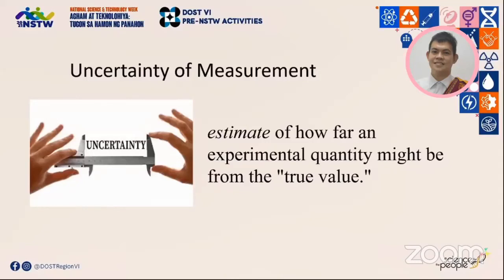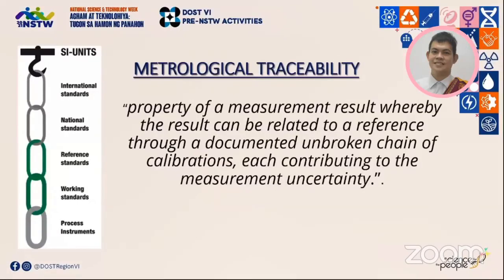Metrological traceability is a property of a measurement result whereby the result can be related to a reference through a documented and unbroken chain of calibrations, each contributing to the measurement uncertainty. Traceability is established through reference numbers that connect calibration results back to the standards used for reference. These numbers allow each measurement made to be traced back to the international standard through an unbroken chain of calibrations. As calibrations move up the traceability chain towards the international standard — the SI — the tolerances become tighter and tighter.